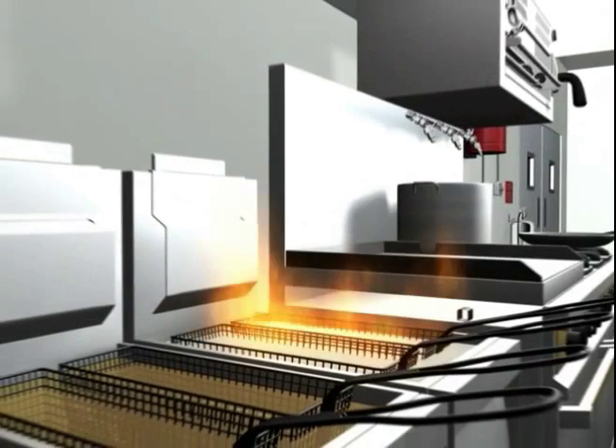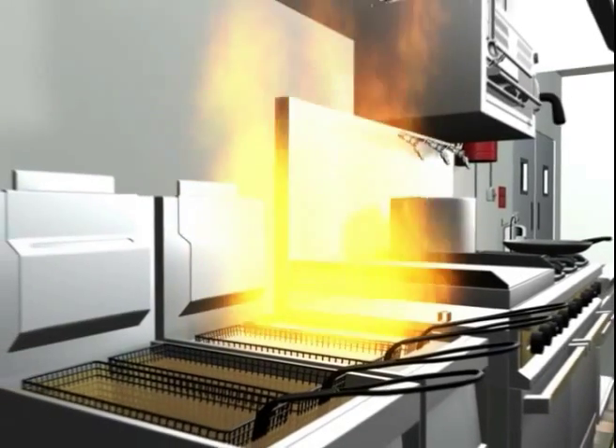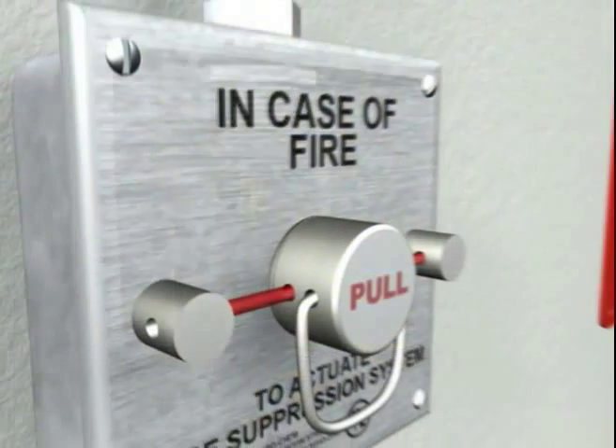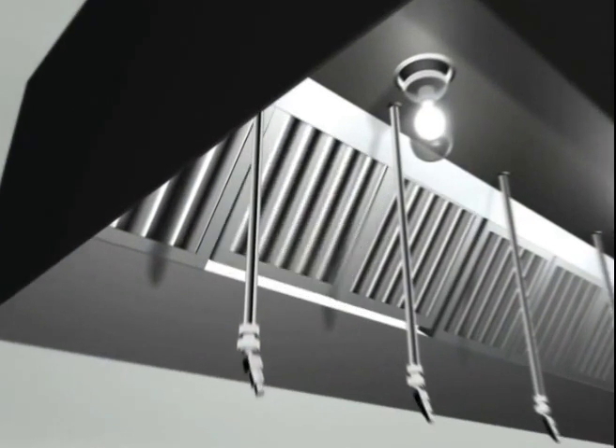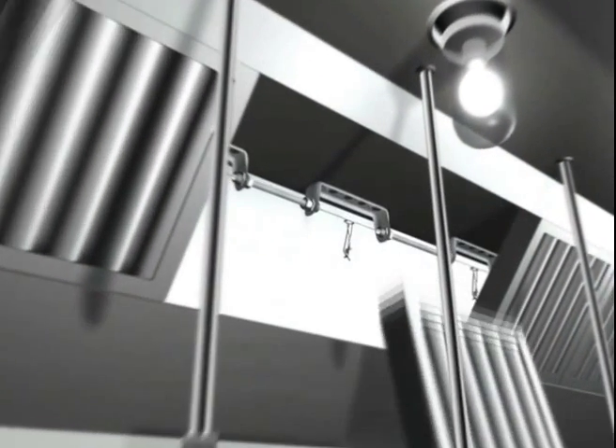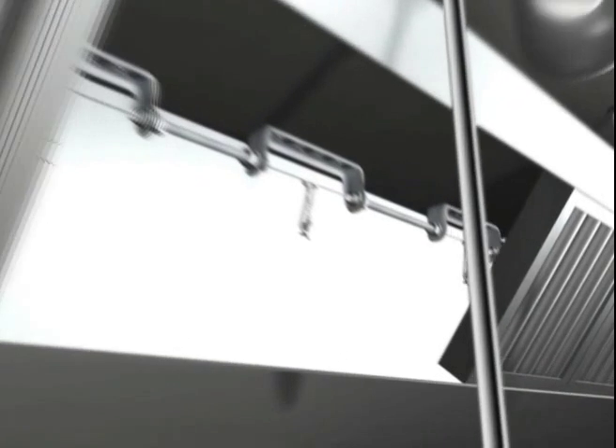In the event of a fire, the Kitchen Knight II restaurant fire suppression system is actuated either by the manual pull station or the fusible link detection system located in the hood. The fusible links are carefully installed and positioned in each duct area and over each hazard.